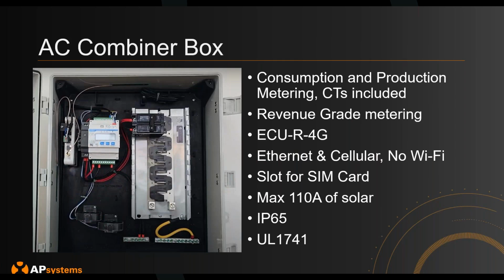I don't know the exact wire gauge offhand for these CTs, but you can certainly extend them. We don't have an official number that we use, but we've tested it up to 100 meters, which is around 300 feet. We've tested at that length before and it's been okay. Another thing to mention is that if you do extend, be careful that you don't switch the phases or switch the wiring of the CTs.